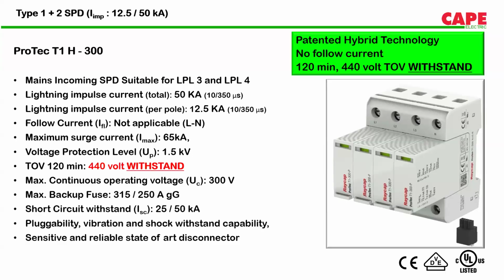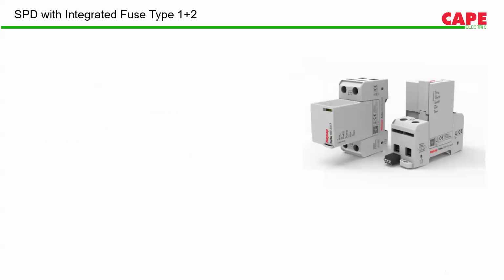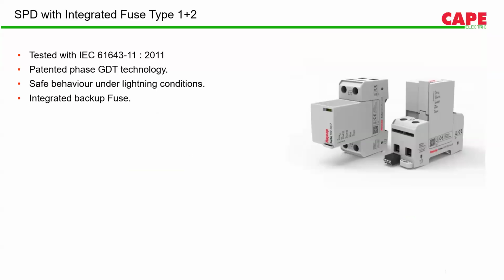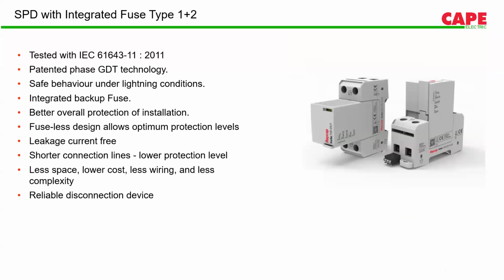What do you mean by leakage current? Leakage current means sometimes metal oxide varistor based SPDs can have a problem of leakage current. So even if there is no surge, a small leakage current flows through the SPD, which reduces the life of an SPD. Now because these SPDs are leakage current free, the life is generally double when compared to the normal SPDs. So these are integrated fuse SPDs class 1+2, which we have earlier discussed in the slides.